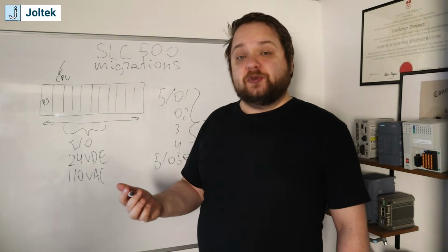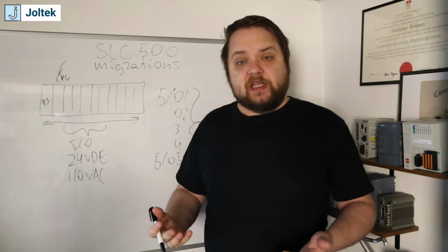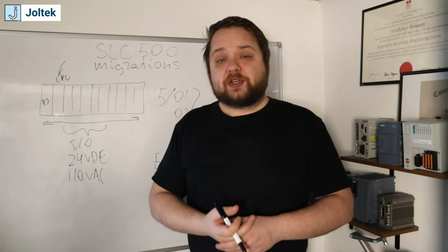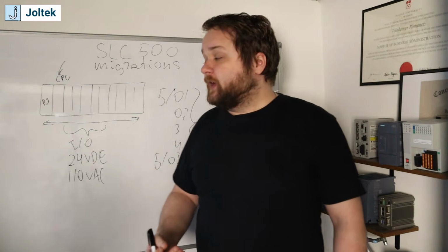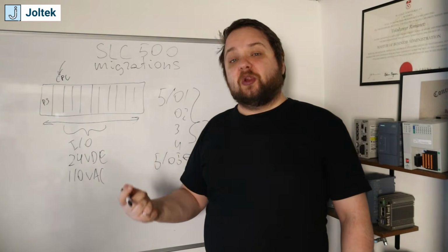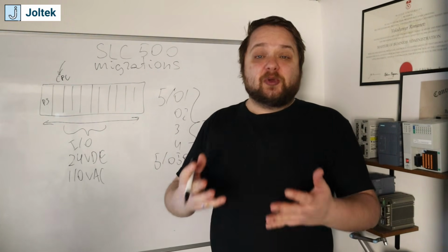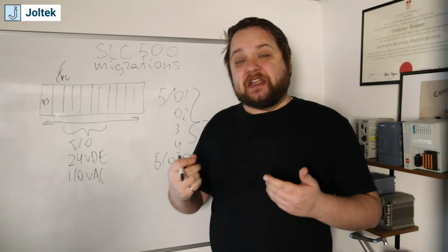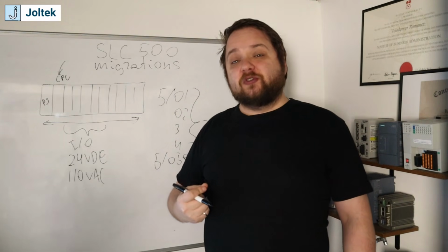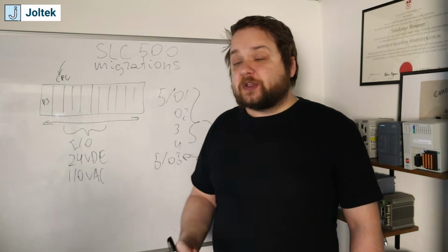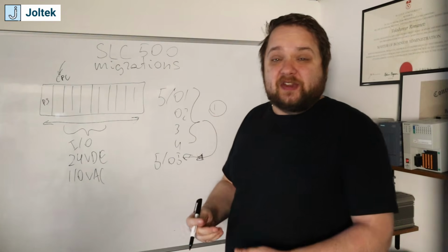What this allows you to do is connect this PLC onto the plant network and allow for, again, remote connectivity and some data collection. You can start implementing message instructions if you have other PLCs maybe reading some information. It does not necessarily solve your problem of having obsolete hardware as well as communication protocols, but it gives the engineers the opportunity to start digging into the program and understanding what is inside of this rack, and what is going to be affected should we migrate to something else. It is usually the first step that I recommend most manufacturers take, as it is the easiest one.